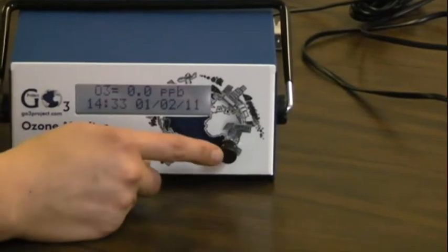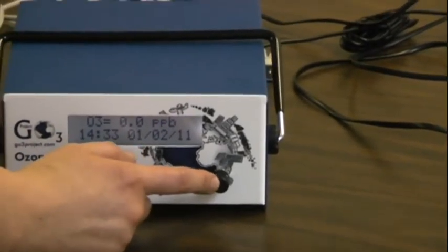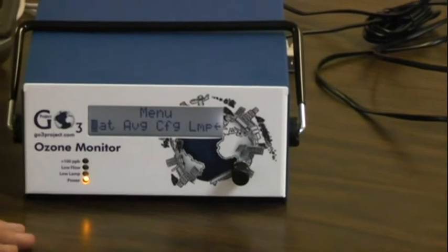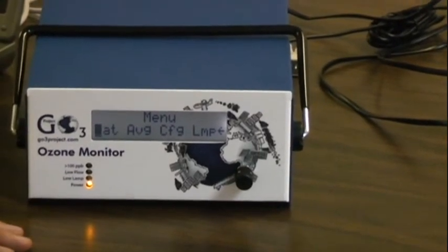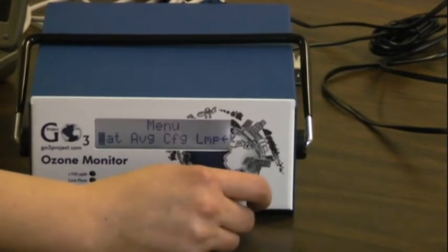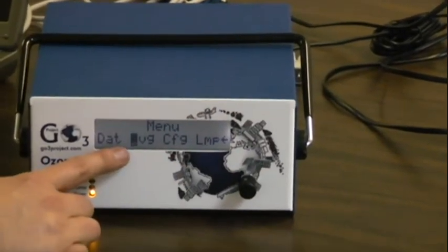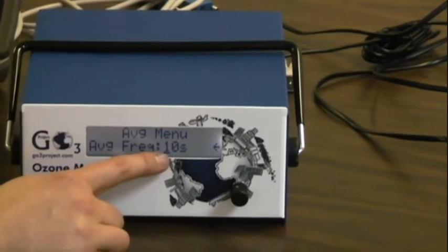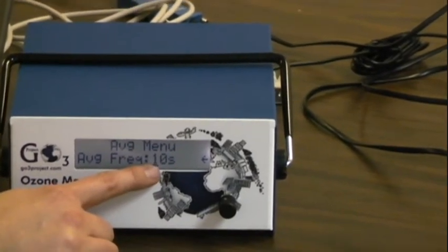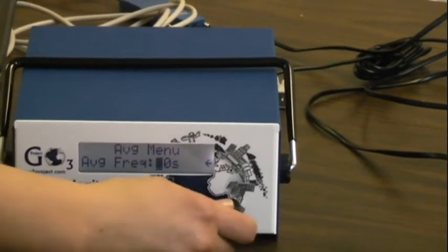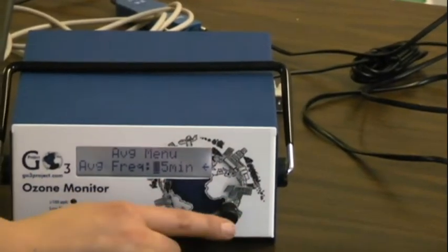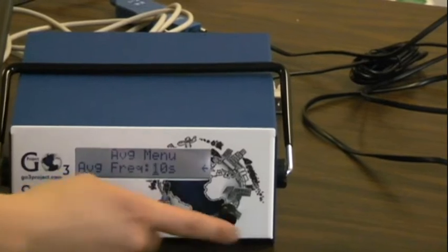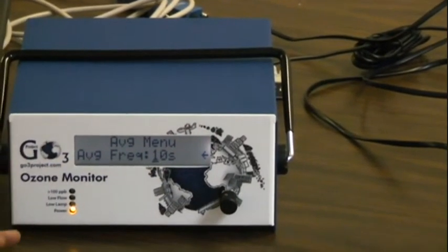To access the ozone monitor menu, you press and hold the black button to the right and you'll see menu come up. We're going to change the averaging to 10 second averaging, which means it will throw a data point every 10 seconds. You want to scroll so your cursor is over AVG and click once to select AVG. Now your cursor is on the frequency. You would click once to change it and then scroll over to 10 seconds and click once to select that frequency.